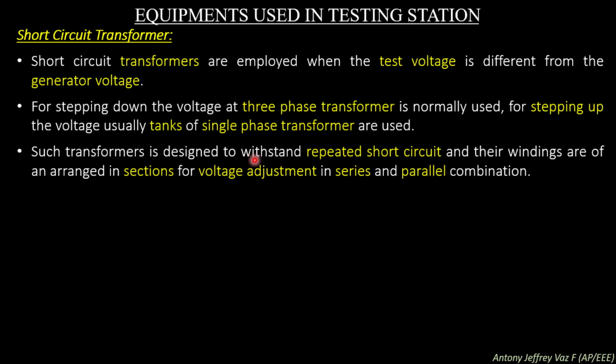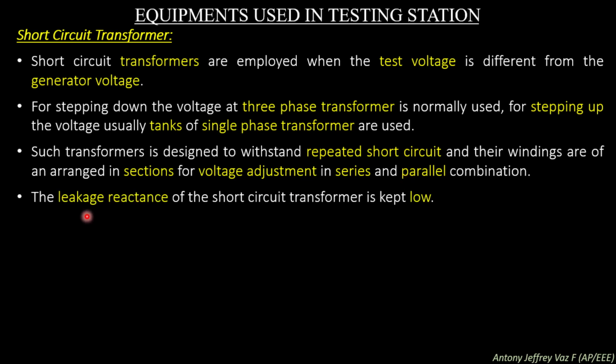Such a transformer is designed to withstand repeated short circuits, and its windings are arranged in sections for voltage adjustment in series and parallel combination. So, the transformer tappings can be changed so that several combinations of voltage can be made with the help of series and parallel connections which are available in the short circuit transformer. The leakage reactance of the short circuit transformer is kept very low.